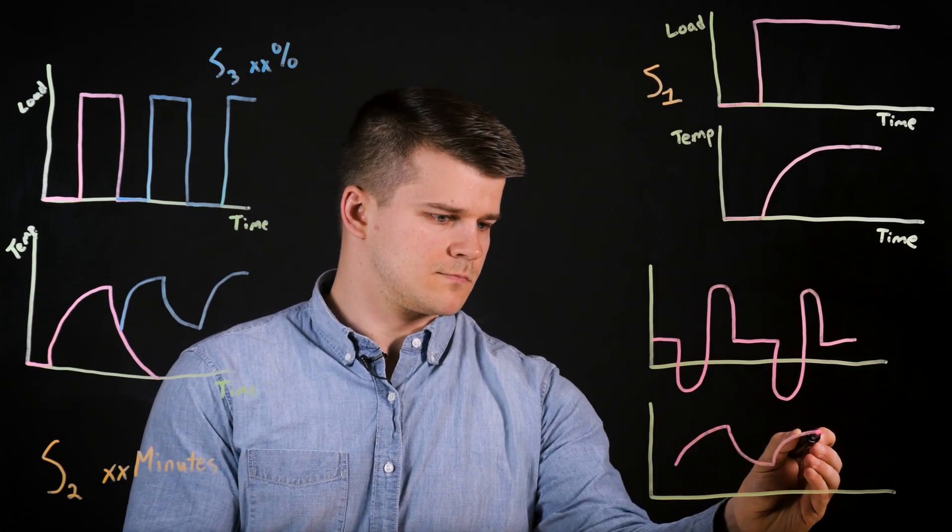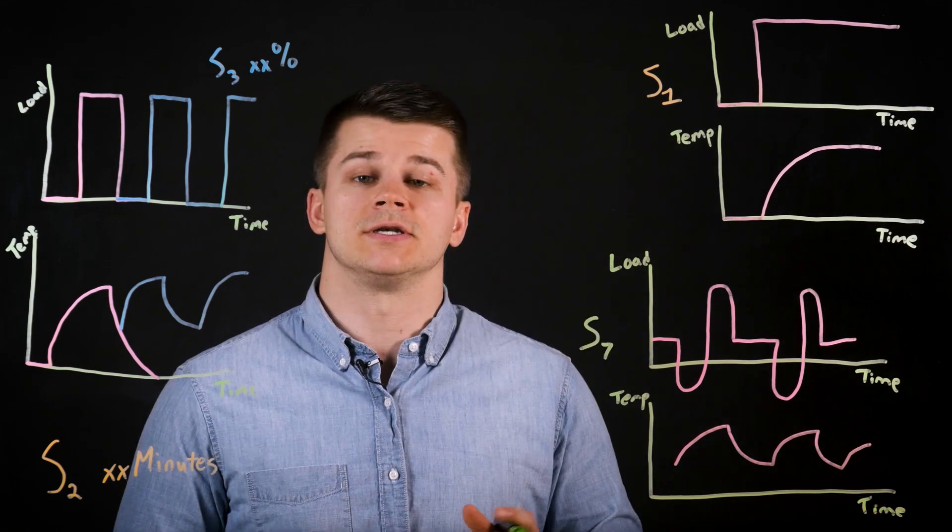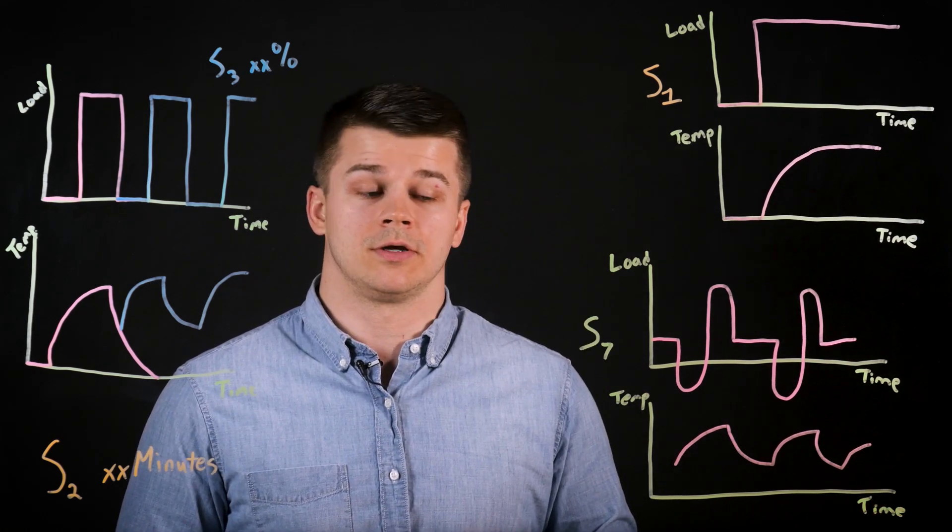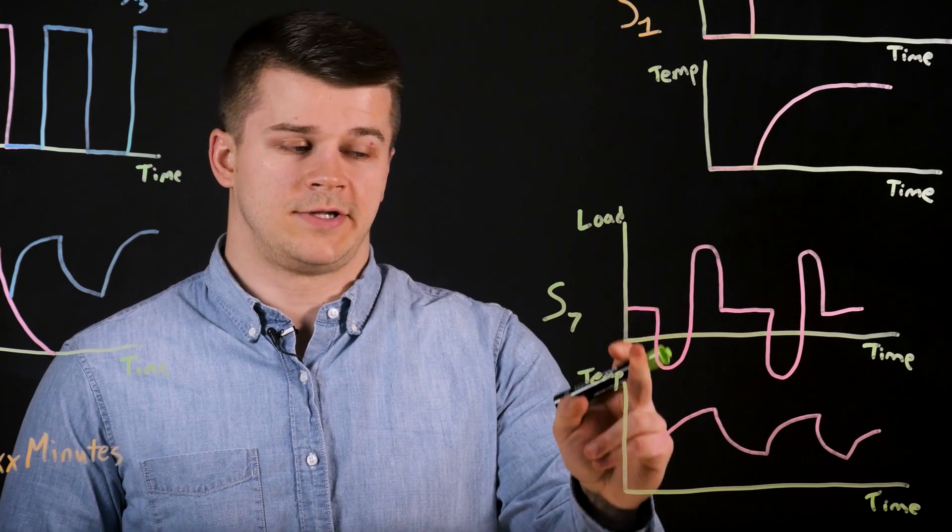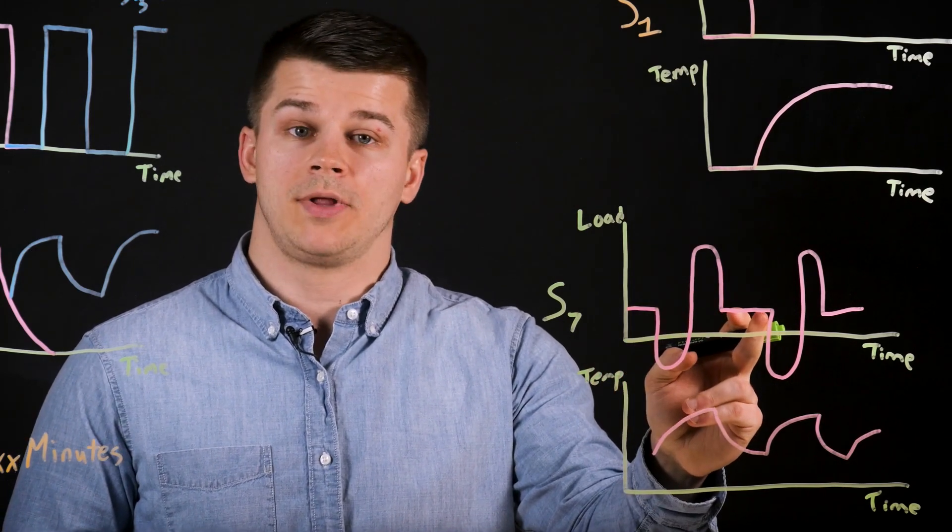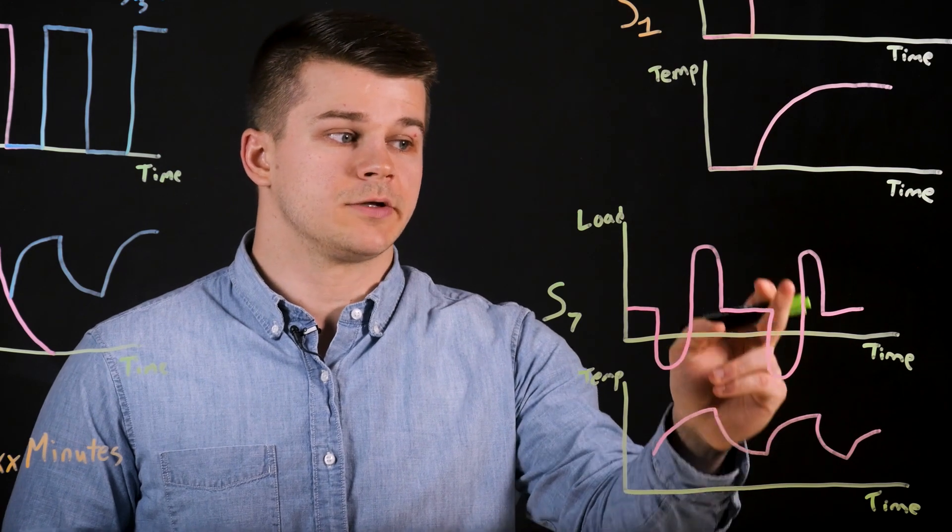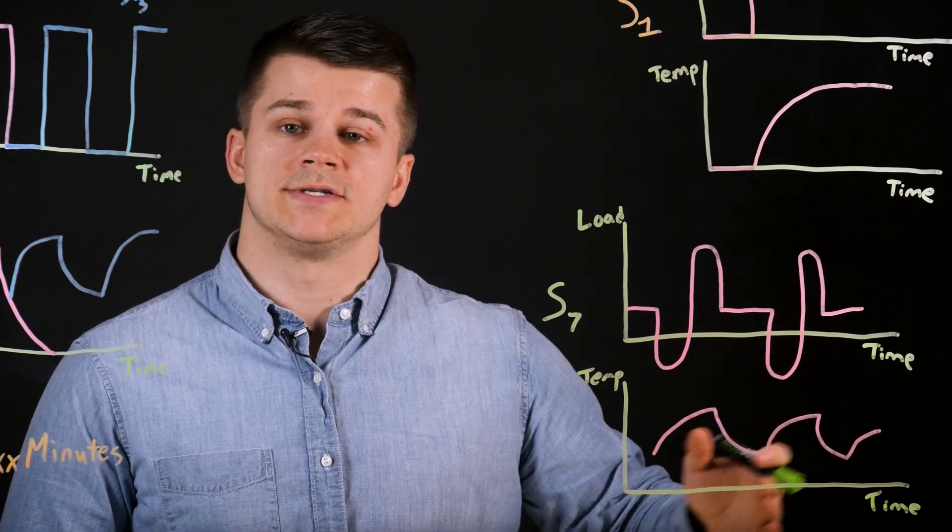The next more complex type of motor duty cycle we'll talk about is continuous operation with electric braking, or S7 duty. In this type of operation, there's electric braking, starting, constant load applied to the motor, and then electric braking, starting, constant load, and it repeats on and on.